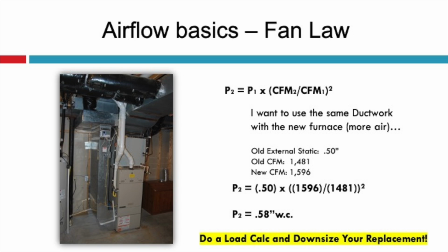So it's probably not going to drastically change the static pressure. But you know me, let's do the math, right? So let's plug that in. Remember the old CFM and the old static pressure stayed the same, right? That's the furnace we're replacing. The new volume of air is 1,596.